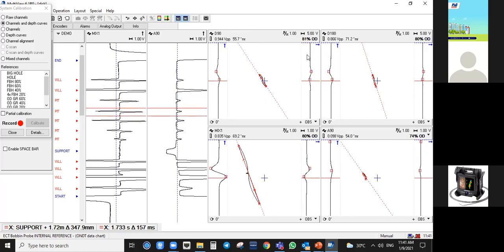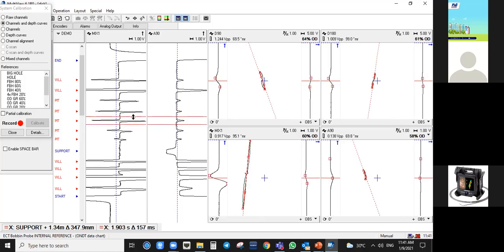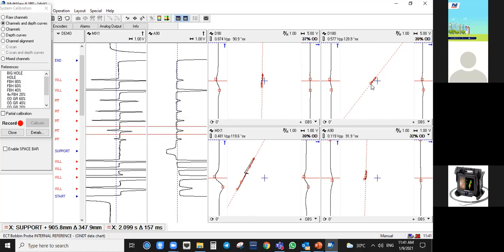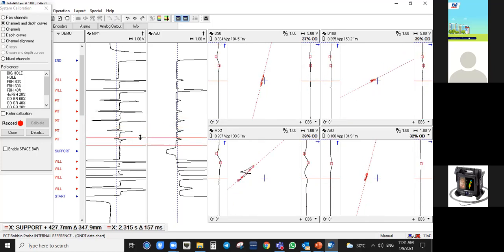Next, you can see here, this is also approximately 1 volt. So you need to see it here, both, and then you'll see it's 81%. Here is 80%. So you go to the nearest one. Okay, so this one is an 80% OD groove, 80% flat bottom hole. Next, same thing. This one indicates a 64% OD. You have at least around 1 volt, 1.2, 1.00. So this one is a 60% flat bottom hole. This one is around 40% flat bottom hole. Okay, you have 0.8 volts here. Then this one would be your 20% flat bottom hole.